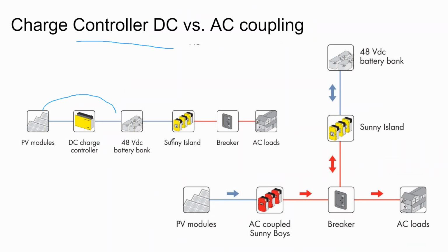You just might find that you're dealing... It might surprise you that not all the charge controllers go up to 600 volts like they do in the batteryless inverter industry. In fact, one kind of advanced configuration I'm looking at for some of my designs now is you can buy 1500 volt modules, and National Electric Code says you can only do 600 volts on residential buildings. But I have one design that's upcoming where the ground mount is going to be very far away from the home, and it's right next to a fence, and it's very easy to build an extension of the fence around the solar array.